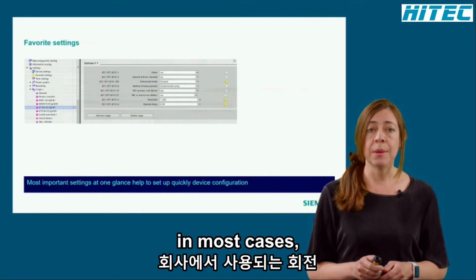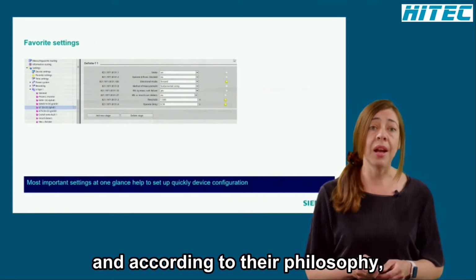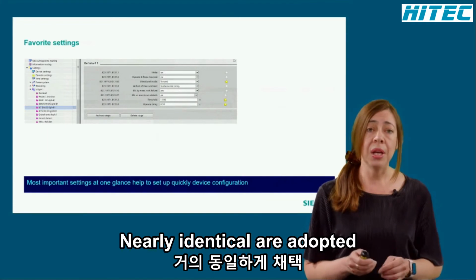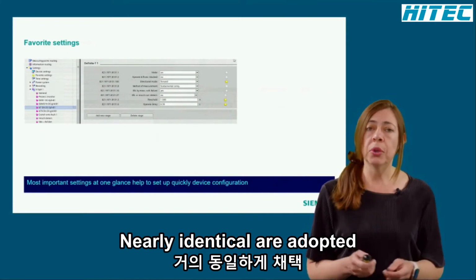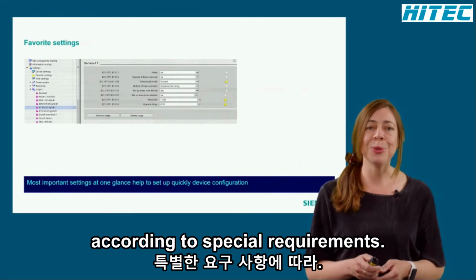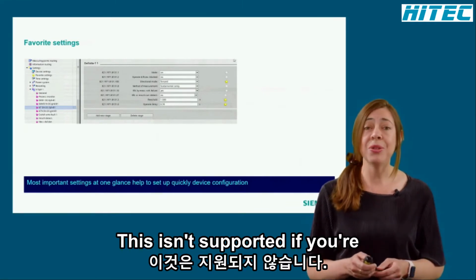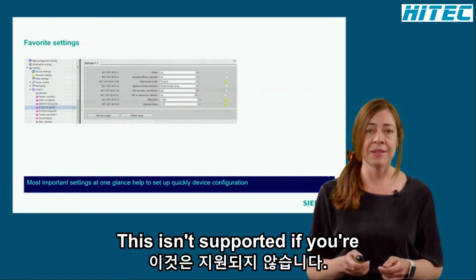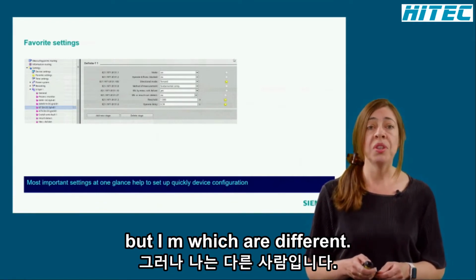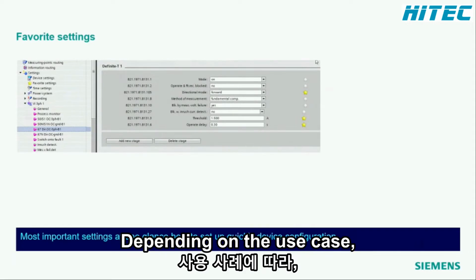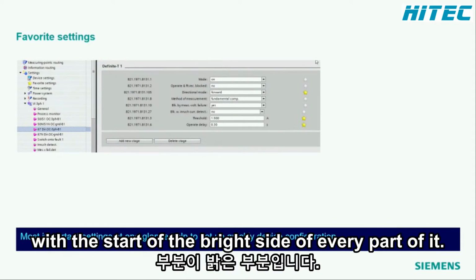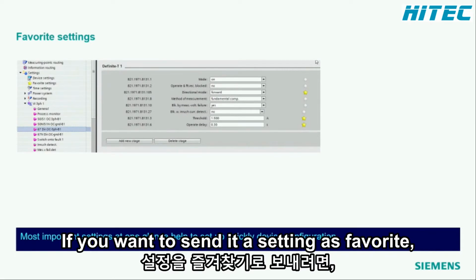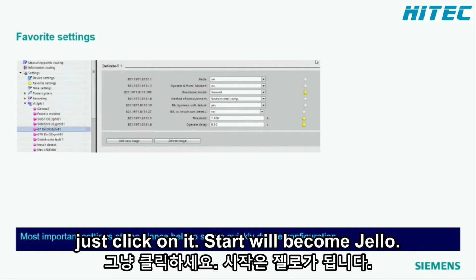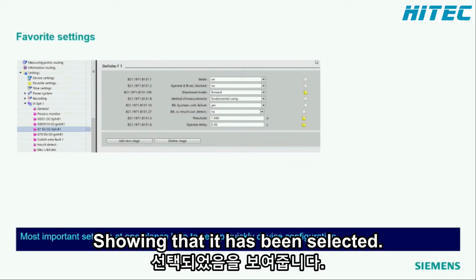In most cases, the protection settings used in a company, according to their philosophy, are nearly identical. Some of them are adapted according to special requirements. This scenario is supported with the favorite settings. The few parameters, which are different depending on the use case, can be marked as favorite with the star at the right side of every parameter. If you want to select a setting as favorite, just click on it. The star will become yellow, showing that it has been selected.